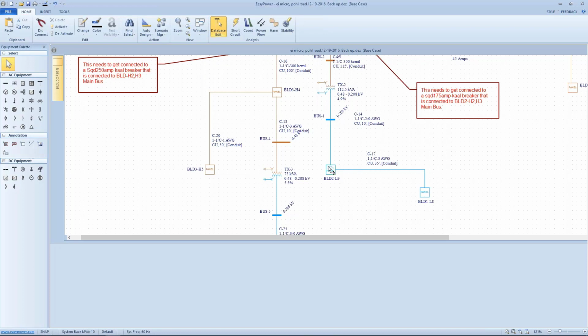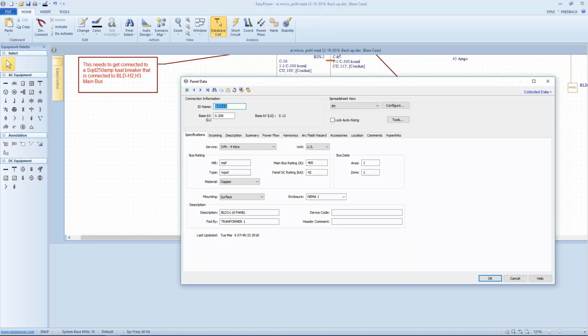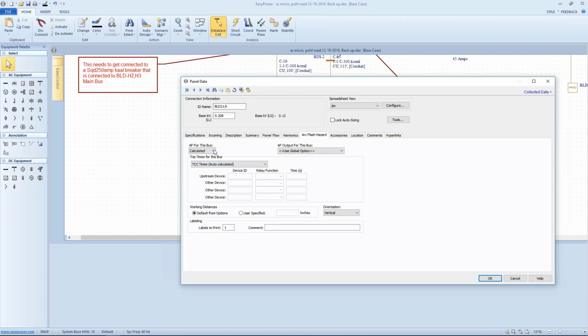I might actually want to rely on the C2 recommendation, which says all 208 volt systems, any system below 250 volts can be rated or worked on with a 4-calorie protective clothing.